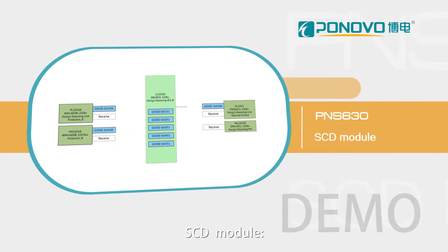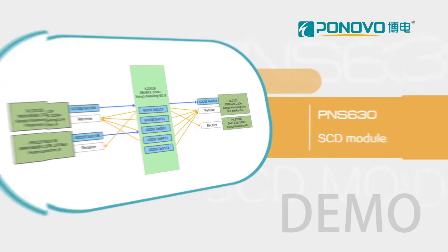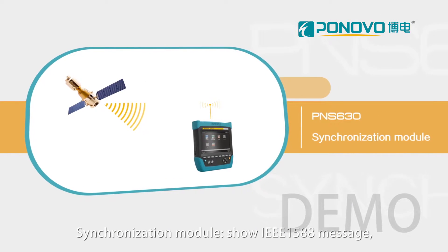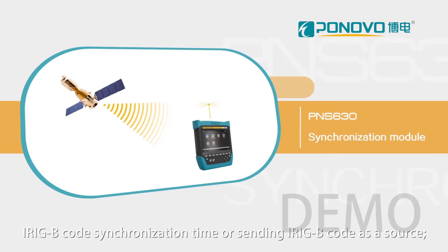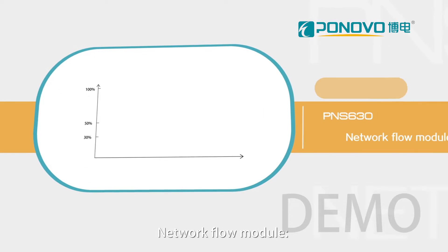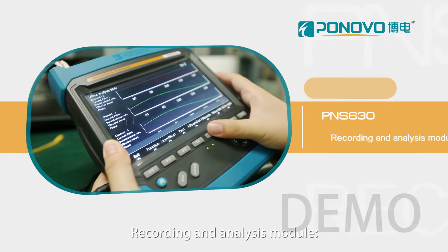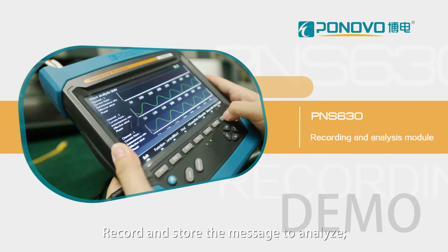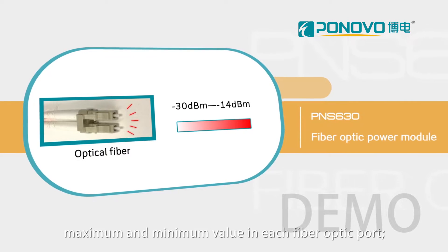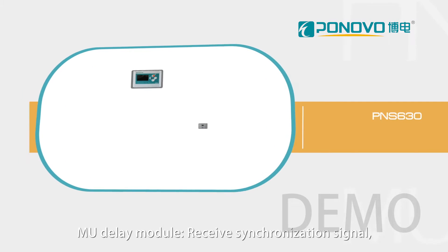The SCD module shows the varying connections between devices and virtual terminals in SCD files. The synchronization module shows IEEE 1588 message and IRIG-B code synchronization time, or can send IRIG-B code as a source. The network flow module monitors the received message flow from each fiber optic. The recording and analysis module records and stores messages for analysis. The fiber optic power module checks the real-time, average, maximum, and minimum value in each fiber optic port.